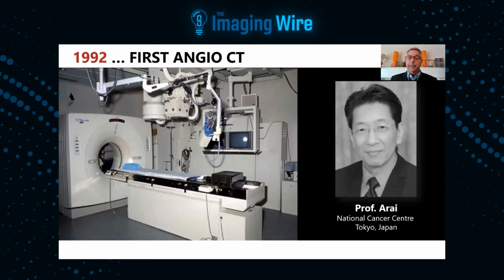If you look here at the first angio-CT that was ever built by any vendor, and this was deployed in 1992 by Dr. Arai, you see here is the father of this concept. And back then we put together an angio room. If you look at just the makeup of this room, it's obviously not as much new technology as you can see from the current systems that we have now. But the big thing is, if you look at the CT scanner, those who are on the call that understand it, you can see that the detector on this CT scanner is maybe 1, maybe 2 centimeters wide at the most.